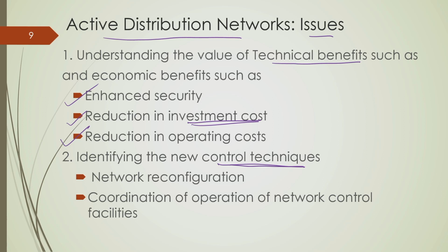Another important issue is that typical distribution networks have only a small number of sensors connected, which would be needed for advanced control and monitoring. Not many distribution networks are fully connected with supervisory control and data acquisition systems, SCADA systems, so it is very difficult to get centralized control of the whole system. That is one of the challenges, particularly in active distribution networks with DG units.